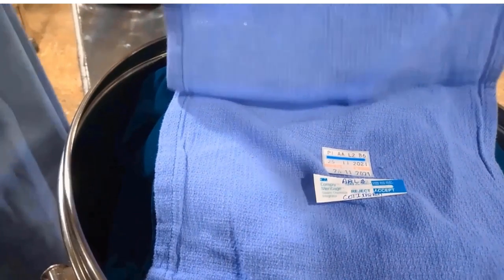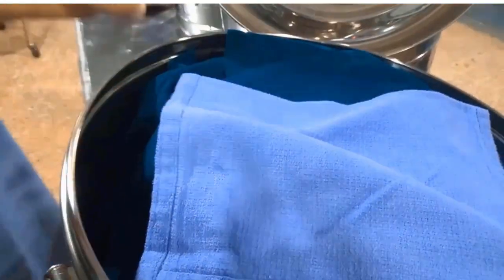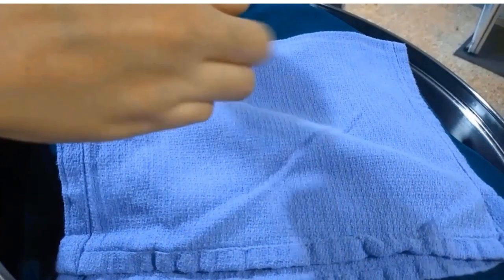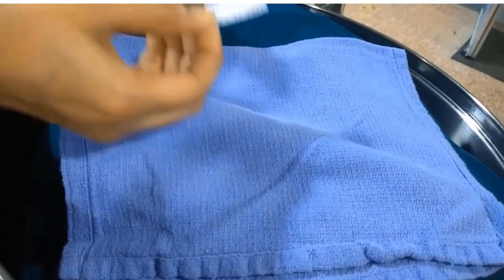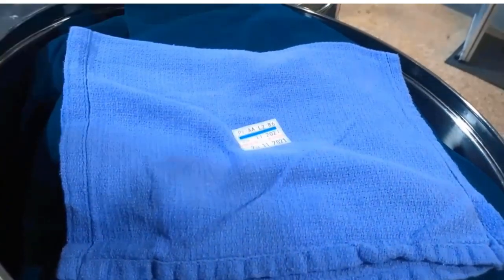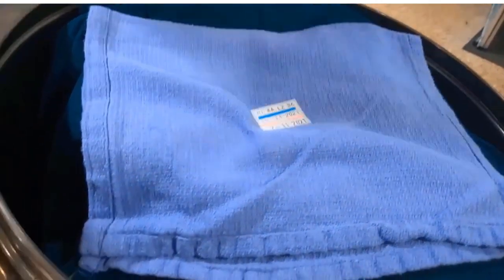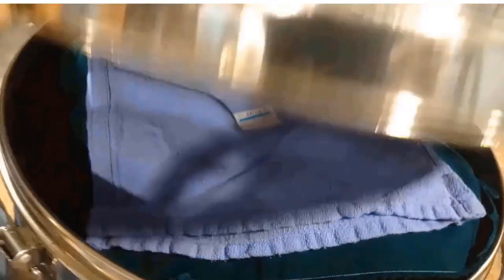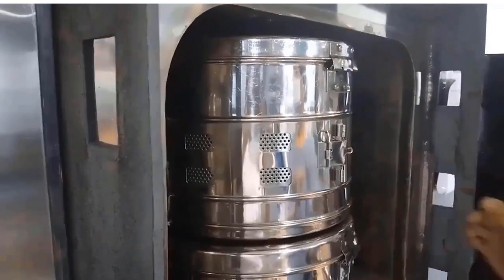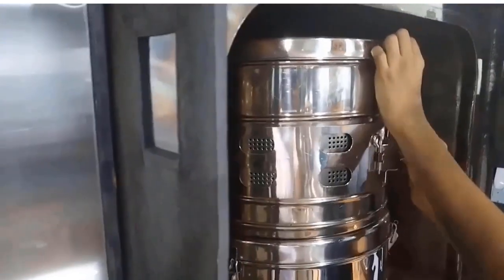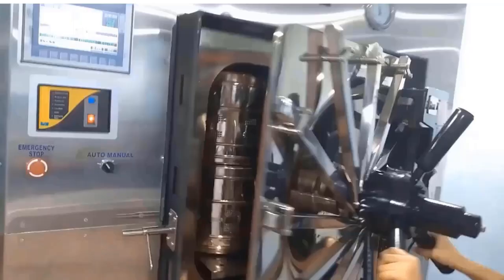Class 1 or 3-line label indicator should be kept in every load and every bin. Do not load liquid and cartons with the instruments bin. In the class 1 indicator, mention person name, bin number, load number, date of sterilization and expiry date. Class 1 indicator should be placed in every instrument set. Before closing the load, check whether the bin holes are open and the indicators are loaded properly.